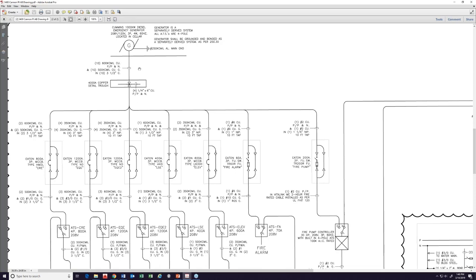People confuse it many times because in many cases, the code refers back to certain sections of Article 230. For example, on the load side of a separately derived system, certain rules that apply to a service apply to that as well. But a lot of people, by mistake, consider an emergency generator source such as utility. No, it's not. The six disconnect rule does not apply to generator power at all. You can put 20 breakers if you want. And I, in fact, checked the UL standard for generators, and they do not have a limit on how many circuit breakers or disconnects you can connect directly to a generator.